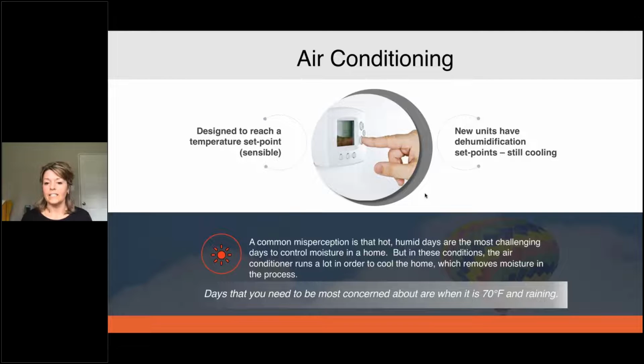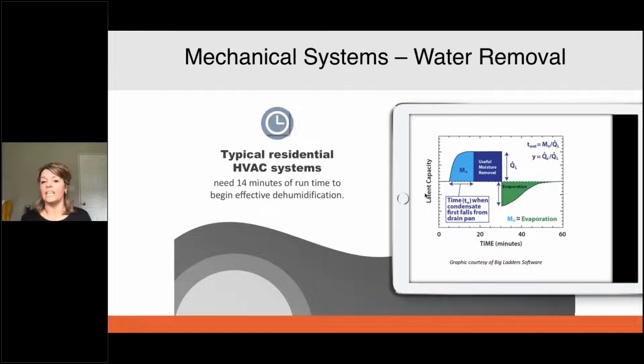And the days that we really need to be most concerned about the relative humidity is kind of that 70 and raining scenario. And depending on where you live, that can last for significant periods of time in the spring and in the fall, where we're not running air conditioning. So our partial and no load conditions is where we really need to be thinking about how am I going to control the moisture. So mechanical systems typically need about 14 minutes of runtime before what is considered effective dehumidification happens. So we need to load the coils of that AC system, and then water needs to start dripping down and going down the drain.